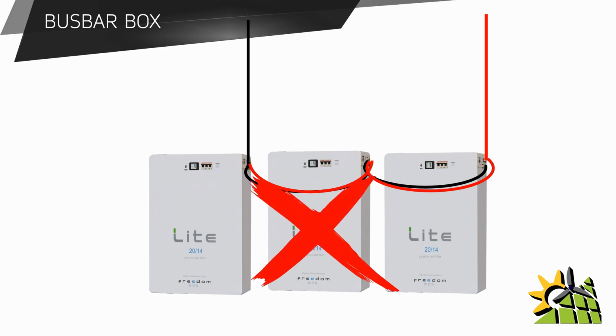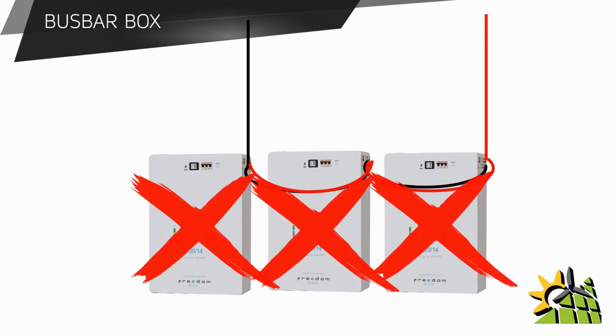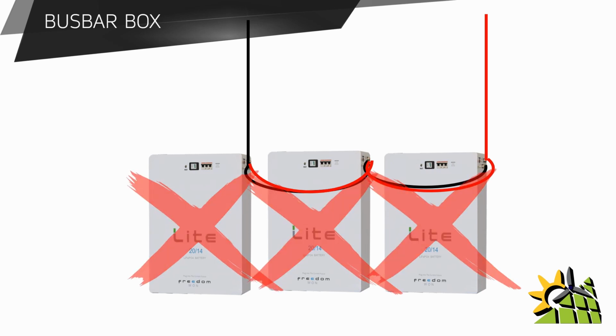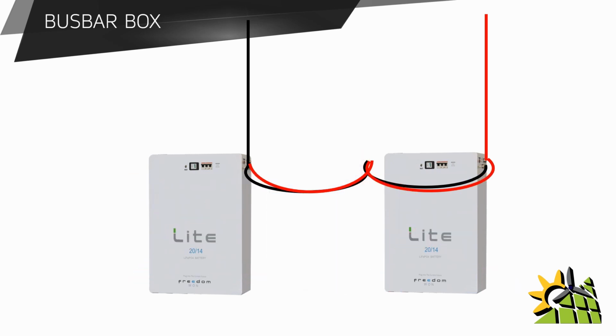Now, if the middle battery were to become faulty, it will affect all three batteries. Now, if that middle battery needed to be disconnected and sent for repairs, you won't have long enough cables to connect the other two batteries together. And although you can move the battery to the middle bank, it would be quite a mission to move these heavy batteries into different positions to accommodate the cables.